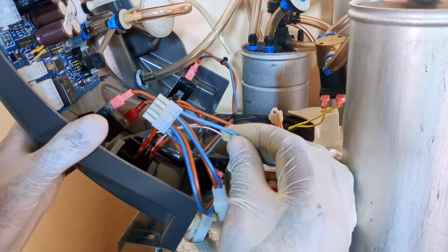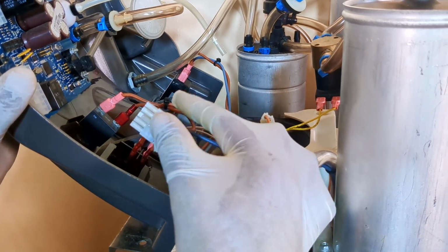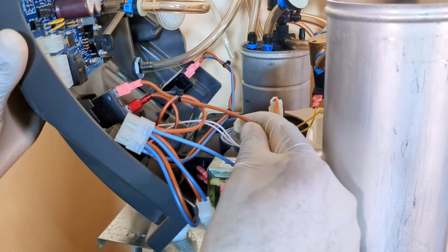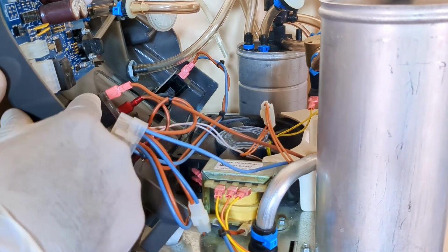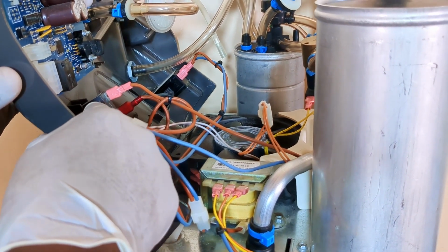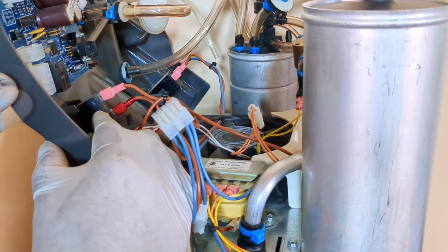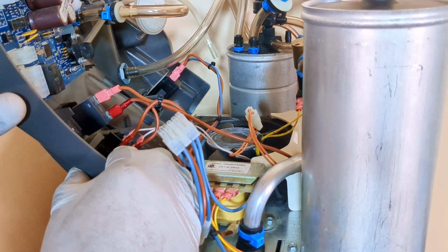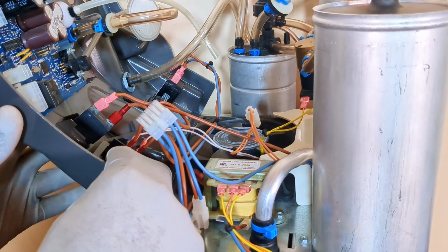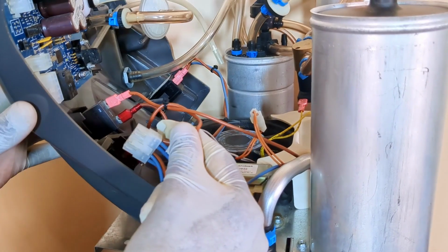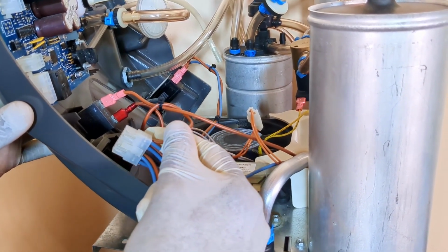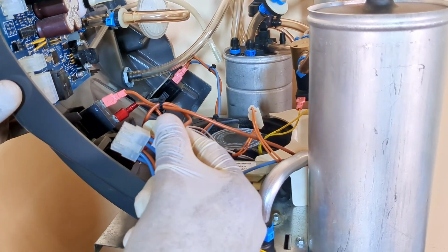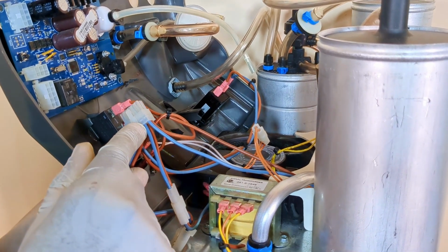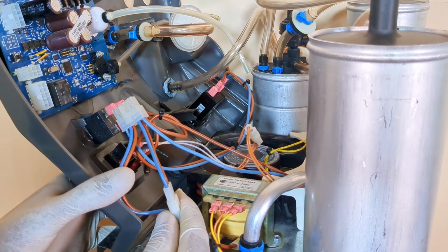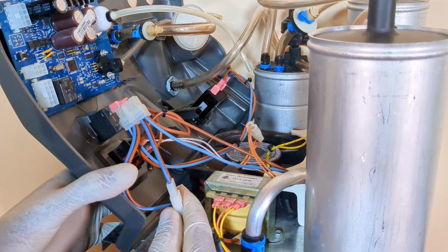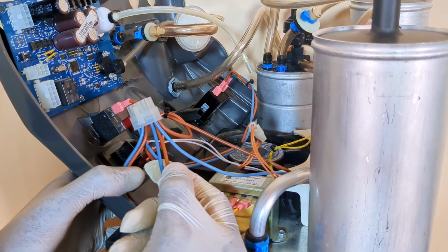The neutral cable is connected directly onto the neutral AC input pin on the control board. The live cable is connected on the circuit breaker. That trips if the cable carries a current exceeding 3 amps. From the circuit breaker, the power is tapped to the power switch using this cable. Now, from the power switch, the live cable supplies the control board with 120 volts AC through this AC input pin.